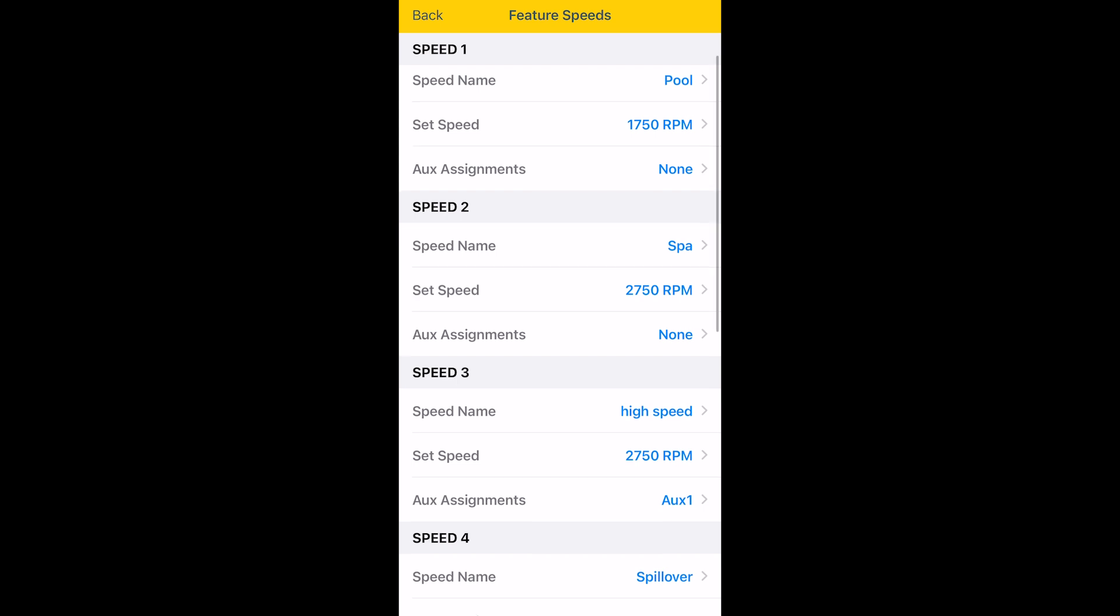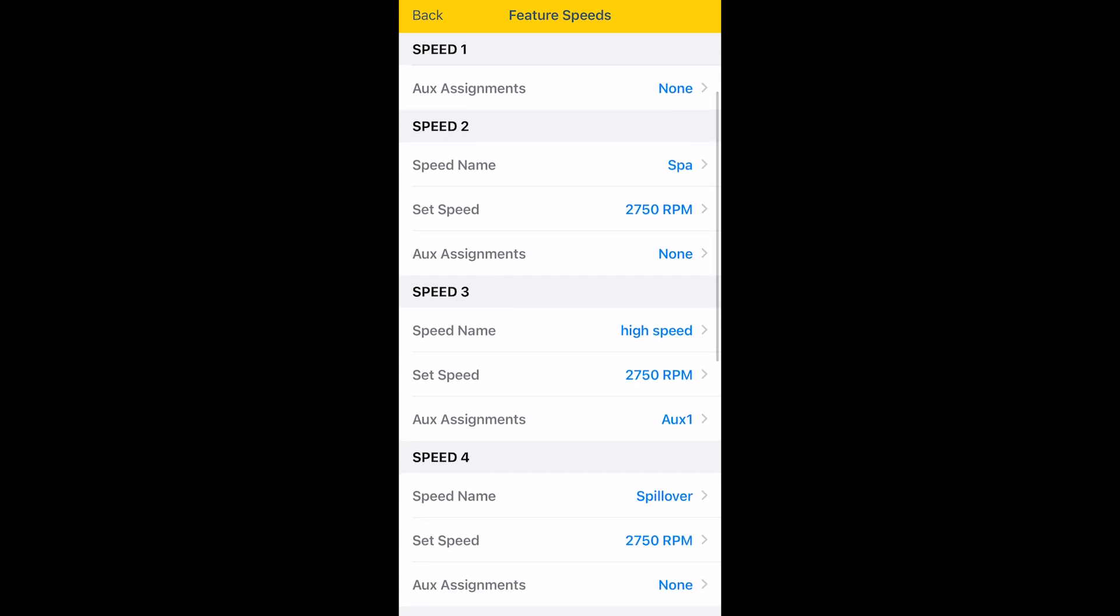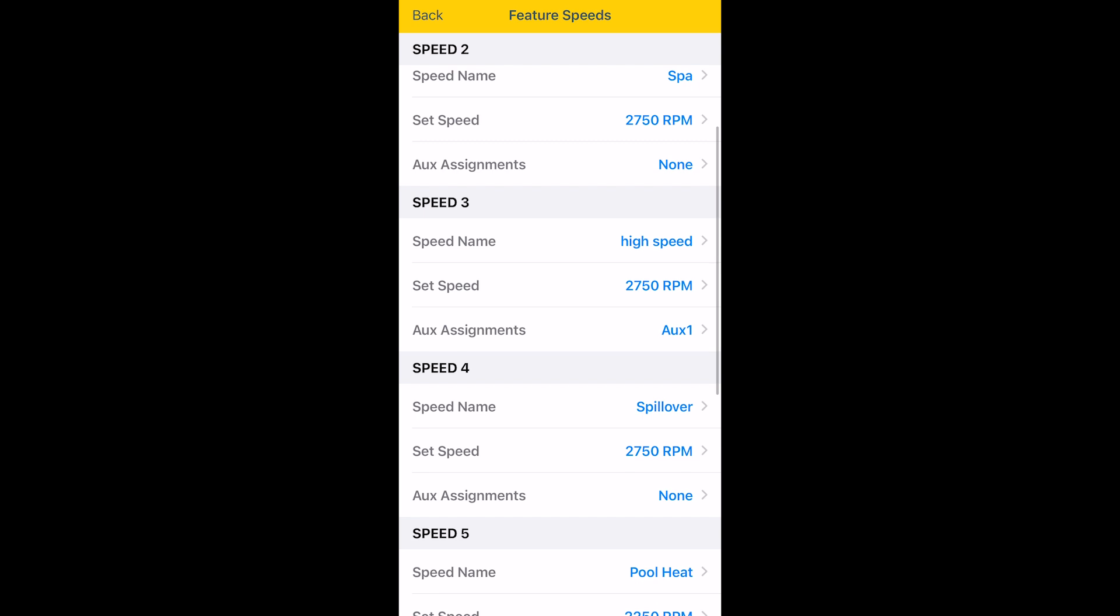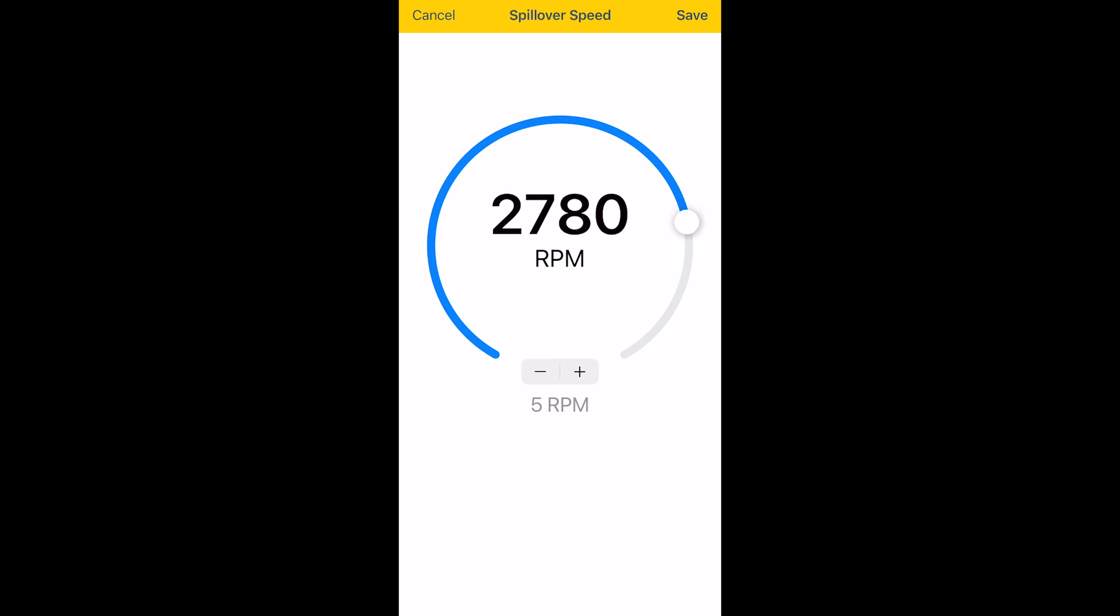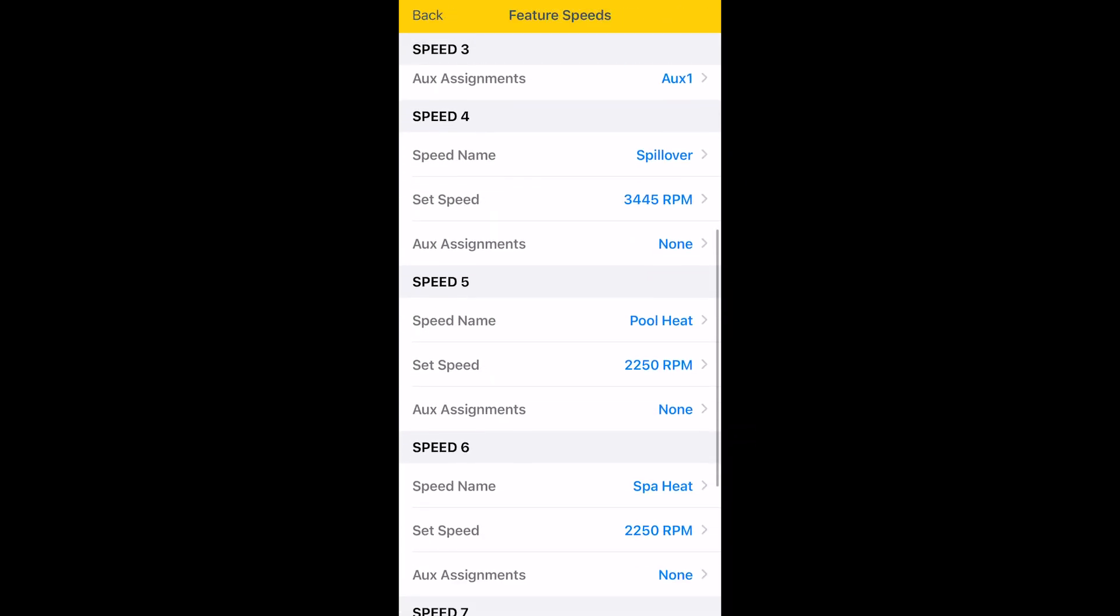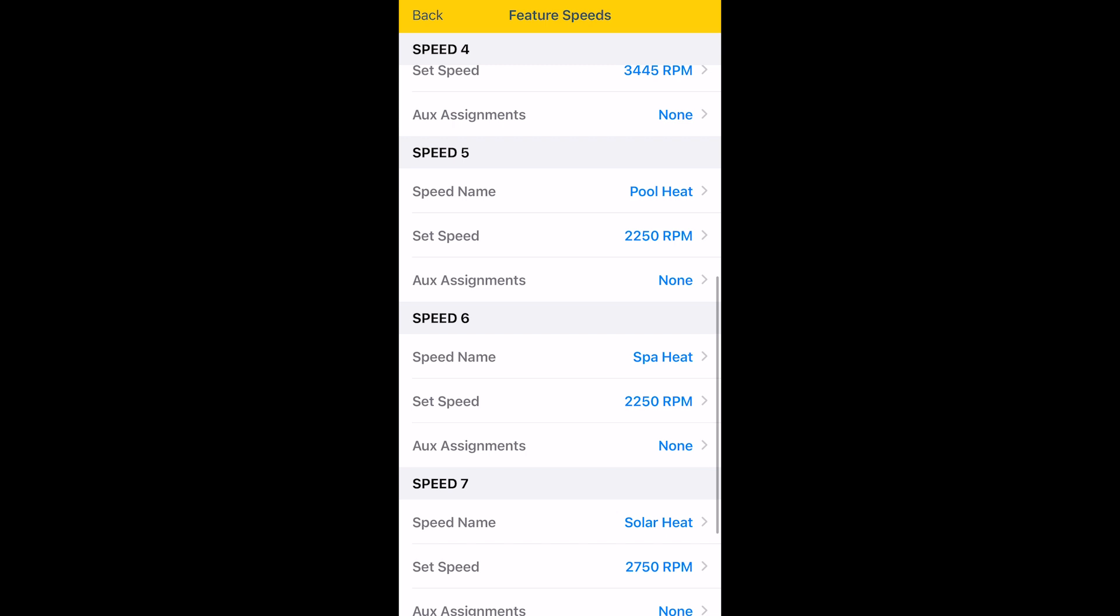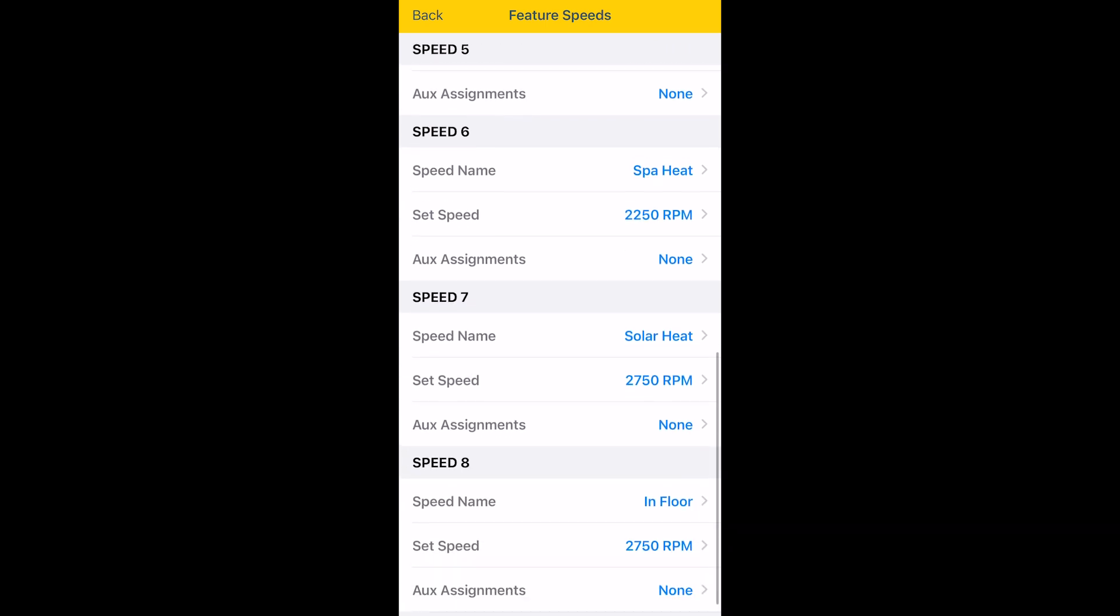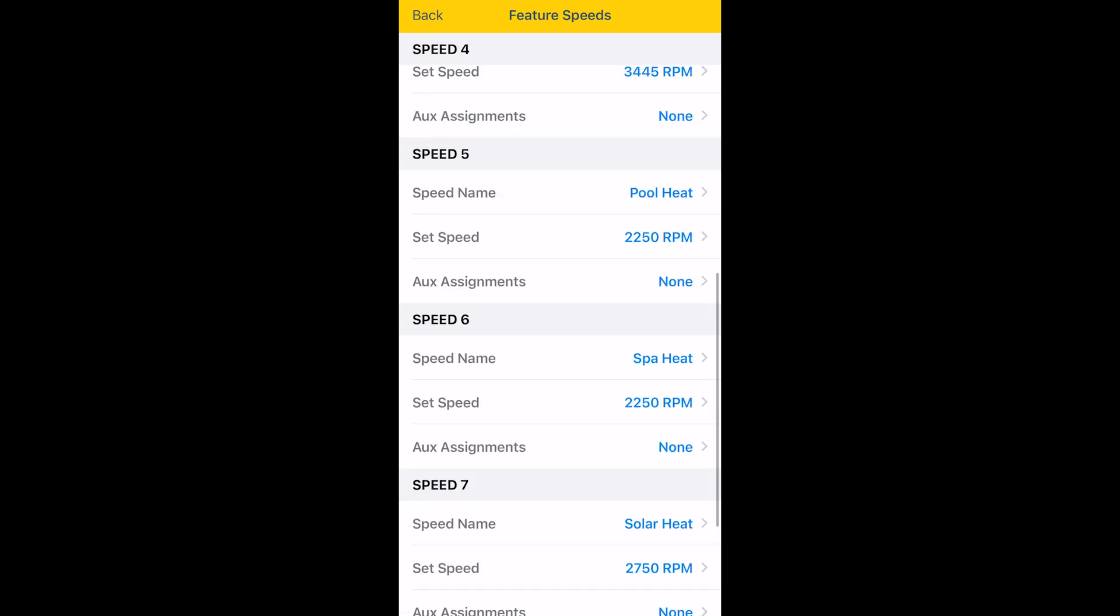Next we want to come over. And you'll notice that we have spillover is already filled in. And there too, we want to have it at a pretty fast speed because we want to make sure that the water is vaulting over the spillway, not running down the side of it. And you may want to crank this up. You can go all the way to the top. It's technically 3450, but it comes up as 3445. And you save that. And you can come up, you can now define your pool heat, your spa heat, solar heat, all of these things that are all set up.